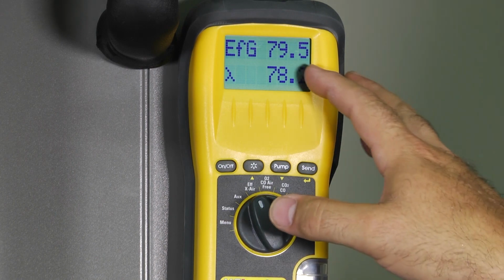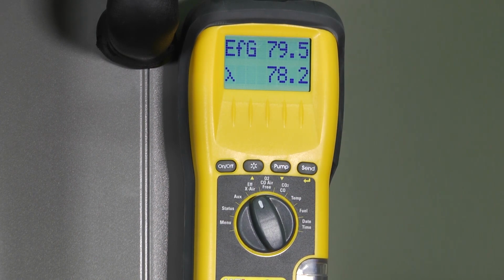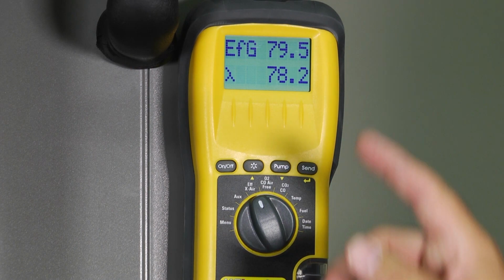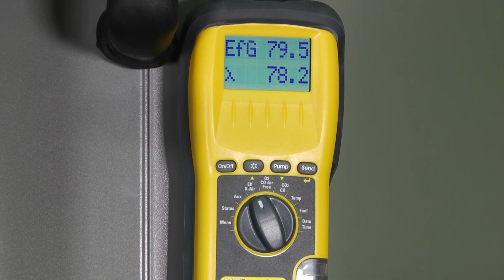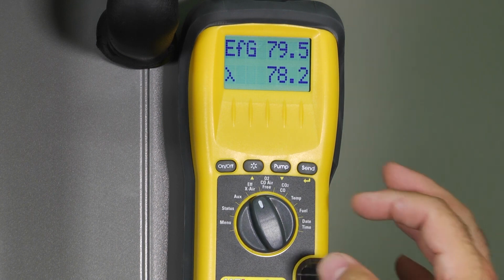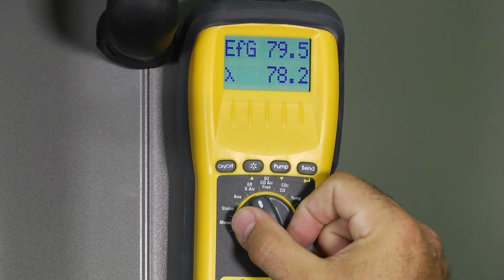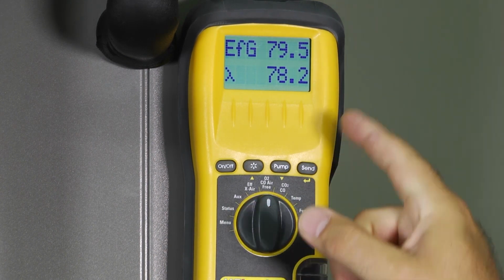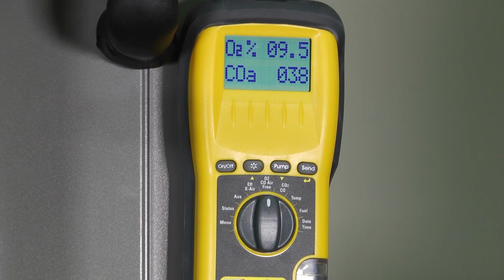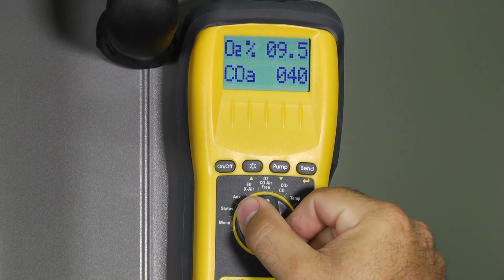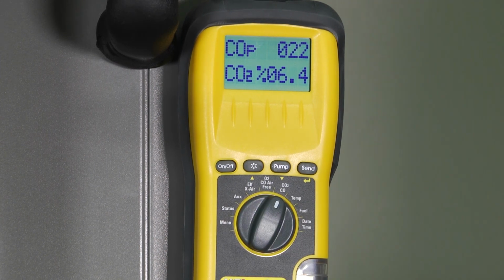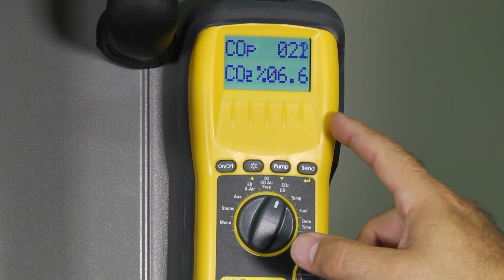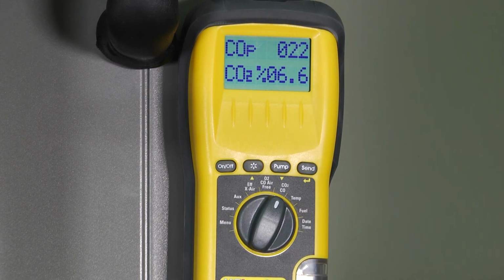I can see that my efficiency in this case is 79.5. Wow, it's an 80% efficient furnace, so I'm almost bang on right there. And I've got 78.2 percent excess air built inside of it. So I'm doing well there without any issues. But when I go back to my CO air free, you can see I'm at about 37, 39, somewhere in that range. But when I go to my CO2, I'm actually at 6.6. So that's my CO2 level.